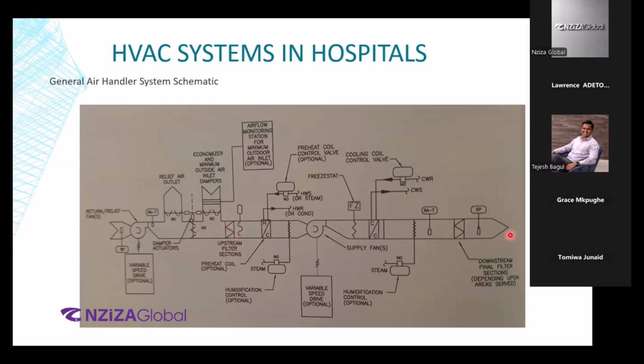All right. And then we have the static pressure sensor in the duct trying to maintain the proper pressurization inside the duct. This is not pressurization in the room. Okay. If we have too much pressure, there might be punctures in the ducts that might happen. Too less pressure, it might mean the duct is collapsing inside itself. Okay. So this is what a generic air handler schematic will look like.